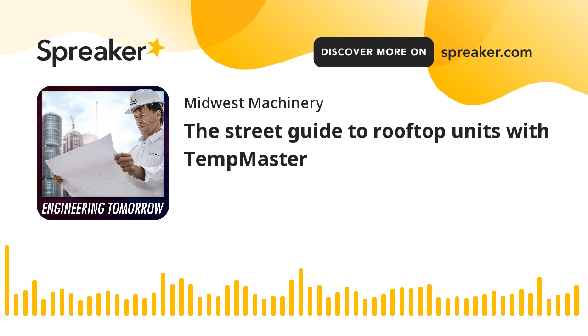Well, I'd certainly say make sure you order the right voltage units. Unfortunately, while it seems very simple, one of the things we end up having to ship replacement units out for is we get on site and they ordered 460 volt units but got 208 or 230 volt. It's such a simple mistake, but it's not one that can be fixed in the field. That's a full replacement job.